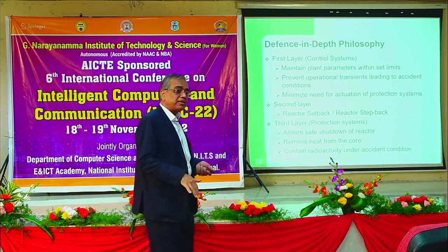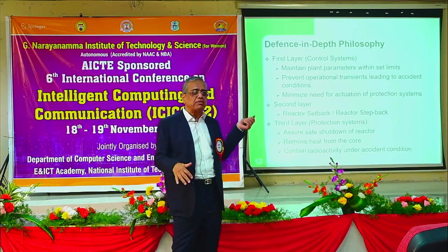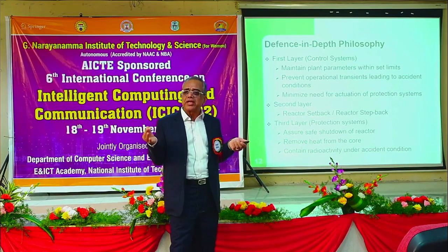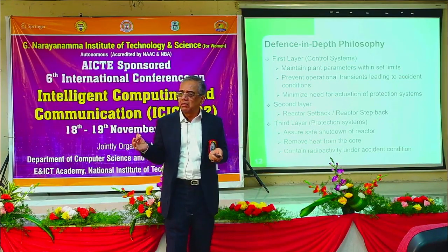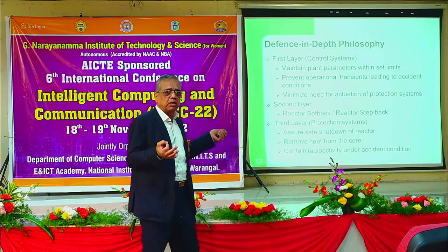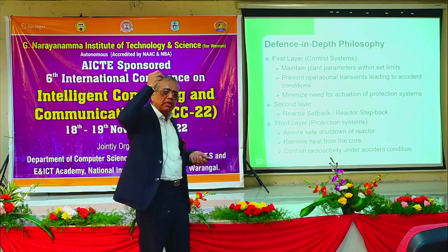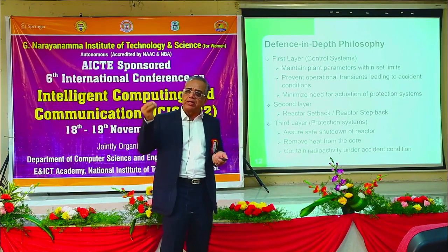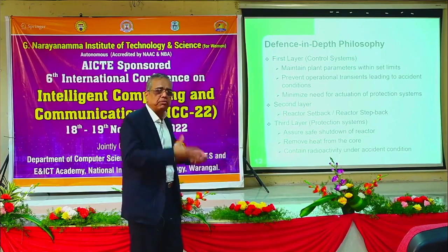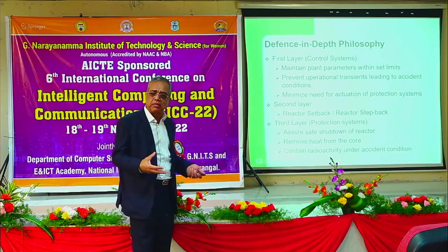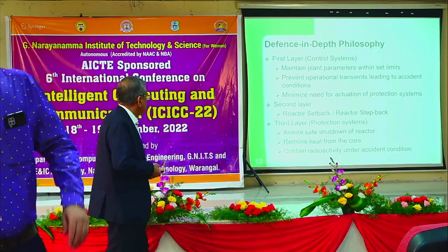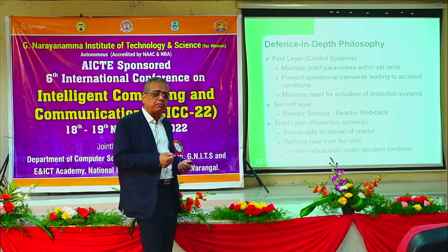There is a secondary shutdown also. We do not only depend on this. Suppose it does not actuate within 1 second, or 1.2 seconds, of some signal being given, then there is a liquid gadolinium nitrate which goes by gravity inside the reactor to absorb the neutrons. Remove heat from the core.